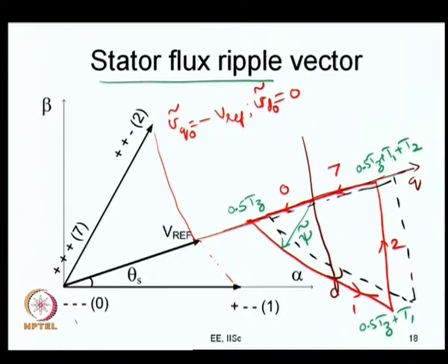The reason is this, that you have these unequal divisions, and I will stress this point more in the next lecture, when I would like to discuss certain alternatives to conventional space vector PWM and how they are different. But for now I am just making this simple point. You can see that there is an error in the q axis ripple, and the peak value of the q axis ripple is more, and therefore, the RMS value of the q axis ripple will also be more. When you add to sinusoidal PWM, you had 1/4 third harmonic injection.